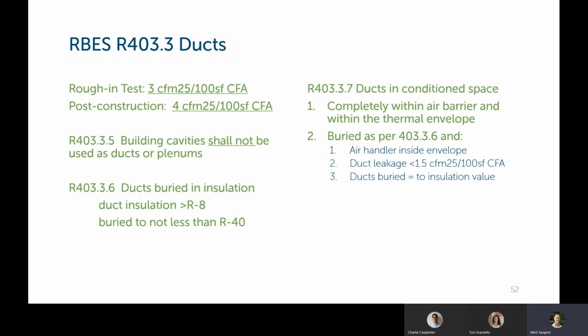So ducts buried in insulation have to have duct insulation greater than R8. And the insulation on top of them needs to be not less than R40. Ducts in conditioned space are completely within the air barrier and within the thermal barrier. So they're defining what conditioned space means. Buried ducts as per 403.3.6 and the air handler has to be inside the envelope. The duct leakage has to be less than 1.5 CFM 25 per 100 square feet of conditioned floor area. And the ducts have to be buried to the insulation value. So that means if your insulation in the attic is R60, the ducts need R60 on top of them.